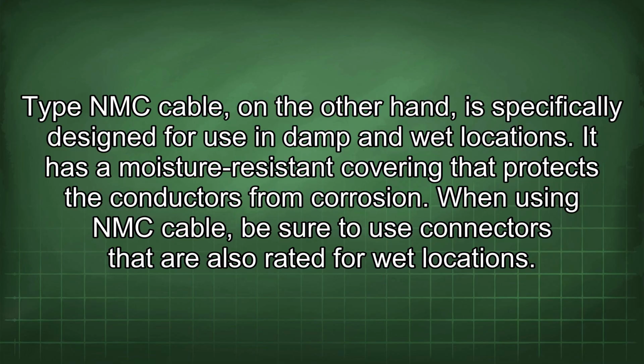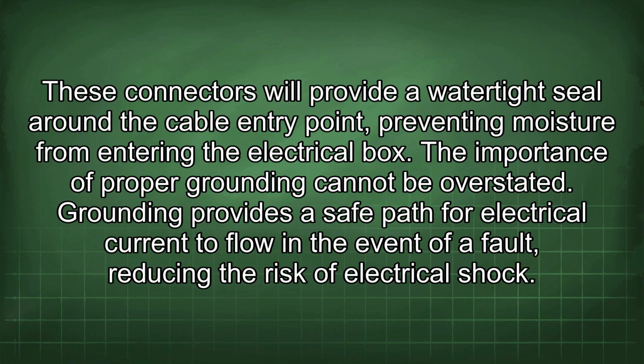It has a moisture-resistant covering that protects the conductors from corrosion. When using NMC cable, be sure to use connectors that are also rated for wet locations. These connectors will provide a watertight seal around the cable entry point, preventing moisture from entering the electrical box.